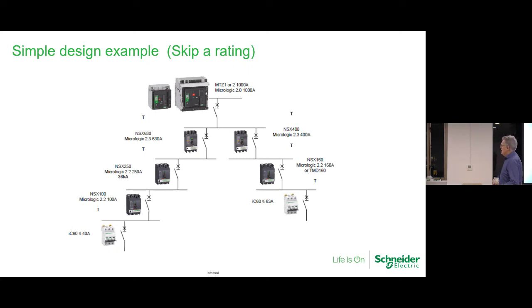You can really see it here, except for one. But you'll see I've got 1,000 amps up here. It's 400 here. So between that 1,000 and 400, there's an 800, there's a 630. So we've skipped two there. So that's always going to be total. 400 to a 160. The next size down is a 250, then 160, so total.